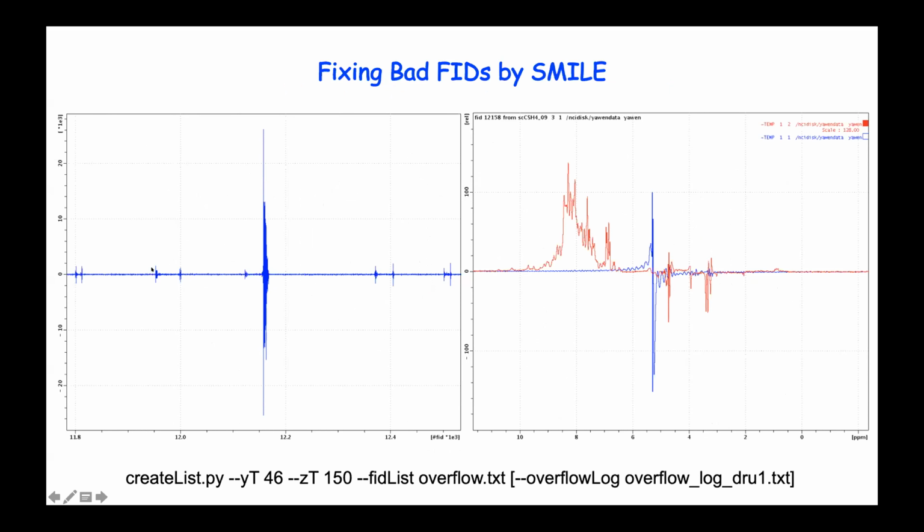So here it's, what is this? Oh, sorry. Hold on. Okay, so you could use that to fix them. So here is a Bruker display for all the FIDs that are corrupted, and some are good FIDs, of course. So it's just one FID after another. And I extracted the worst FID, Fourier transformed them, you see in blue here, relative to the first data points, which is good.